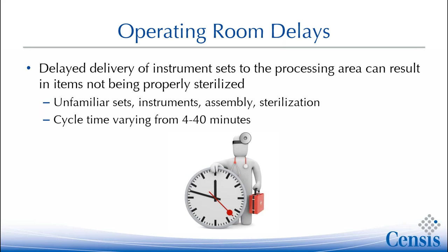Other operating room delays: there are many procedure-specific loaner sets that contain implants. AORN and AAMI both recommend that you do not use immediate use steam sterilization, or what we used to call flash sterilization, for any implant. Rather than using immediate use steam sterilization, it's good to use the exception form for premature release of an implantable device or tray that comes in the AAMI ST79 book. If you don't have the AAMI ST79 standards, you need to get that. It is in the back, in an appendix, I believe A or B, and I can't tell you which one, but it will be back there in the book.